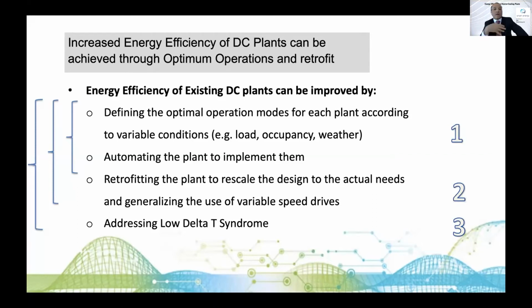Consecutive levers. The first one is what we would call automation, digitalization, and a way of automatically having the district cooling work all the time at optimum set points, which is making the district cooling adapt to the load, to the varying load across the year, across the day, with COVID, certainly. So we need district cooling to be much more versatile and adaptable to the changing load, and also to the changing weather conditions. And increase or generalize the automation of the district cooling so that it adapts automatically without the intervention of the operators. And this is what we have implemented in a few district cooling plants in the region, and we would be very happy to share with you the results of that.